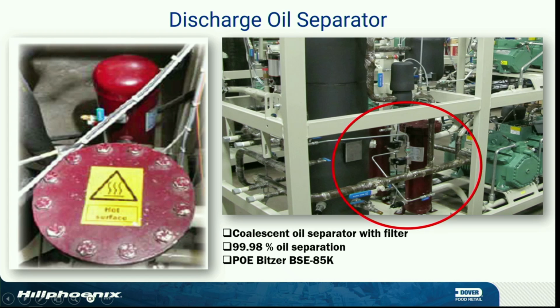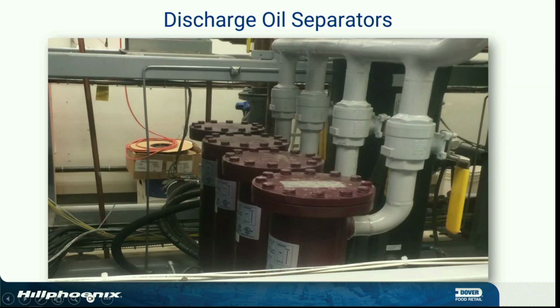This is a Temp-Right. That's our reservoir. That's our separator and our reservoir here. Reservoir separator. This was a big rack. I don't know where this rack was, Rusty. This is an ice rink in Anchorage, Alaska, with a combination booster overfeed. Notice we have four separators because of the design at the time. They needed to have four for the flow of the gas. All right. So today they've got some bigger ones out there. Everybody's come up on board and is developing more technology, bigger operating capacity. So as we go forward, we're getting bigger and bigger.